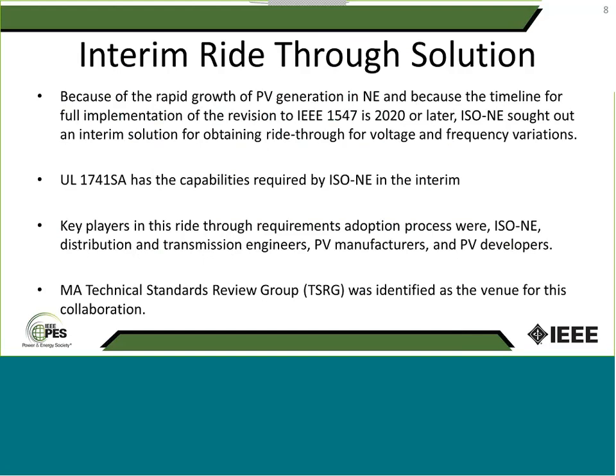What was the interim solution? ISO New England said we cannot wait for the IEEE 1547.1 to be published. And just to give you a little bit of background on 1547.1, that's basically a standard for testing, conformance and compliance for DER. So if you, as a DER manufacturer, say my generator is compliant with 1547, you have to make sure that it passes the tests identified in 1547.1. It's a standard. It's not like a guide or recommended practice. And once we published 1547, most of the resources have been put on revising 1547.1, and we're in the process of revising the standard right now.